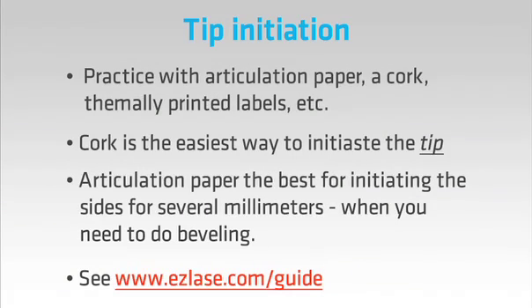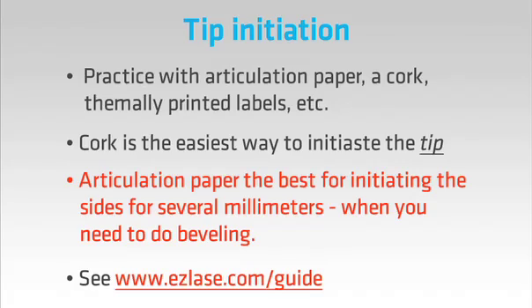Initiating the tip is not difficult to do and there is a nice guide for this on the Biolase website. You can practice with articulating paper or cork or even thermally printed labels or supermarket receipts. Cork is probably the easiest to start with for most procedures where you want to initiate the end. Articulating paper is best for initiating the sides for several millimeters for beveling. Interestingly, one of the most common reasons for service calls for diode lasers is because the user has forgotten to initiate the tip and then tried to cut. All that happens is heating of the surrounding tissue without effective ablation.